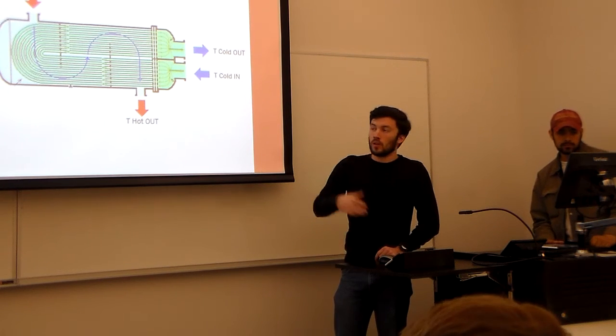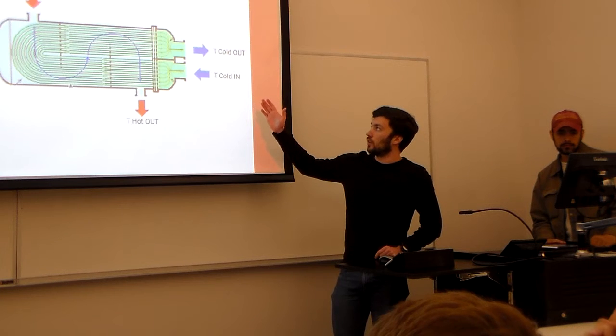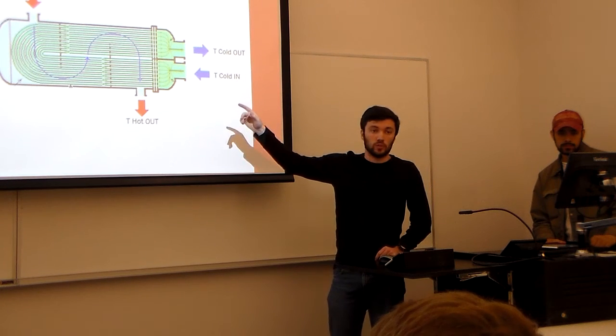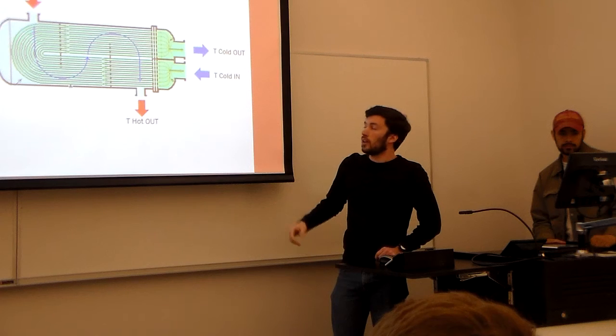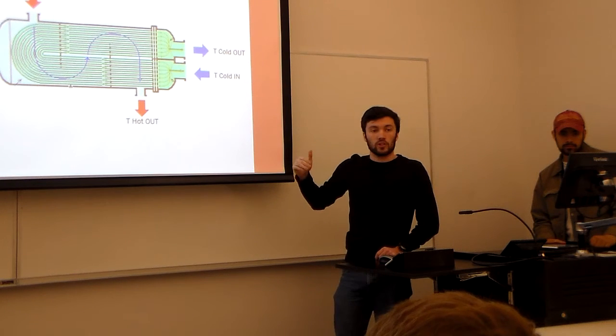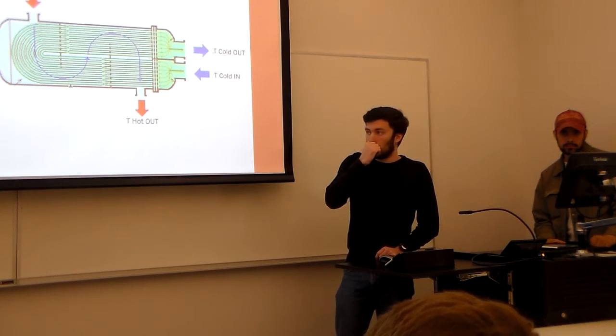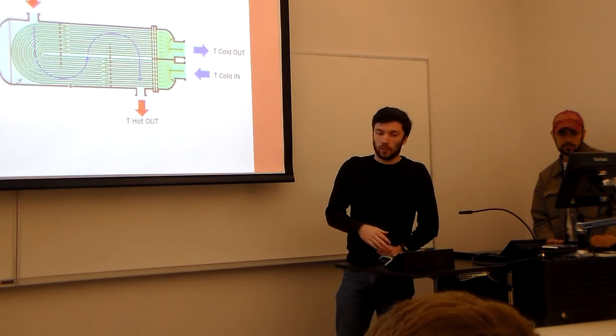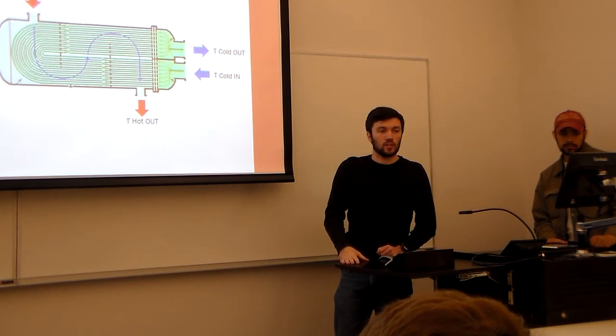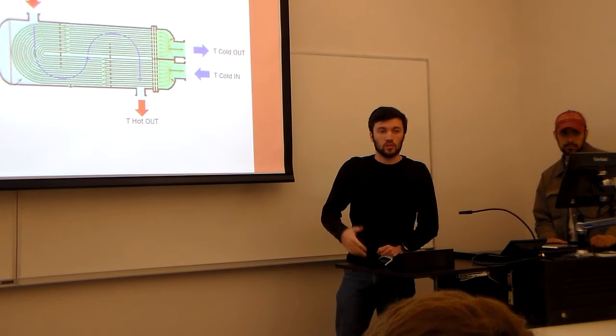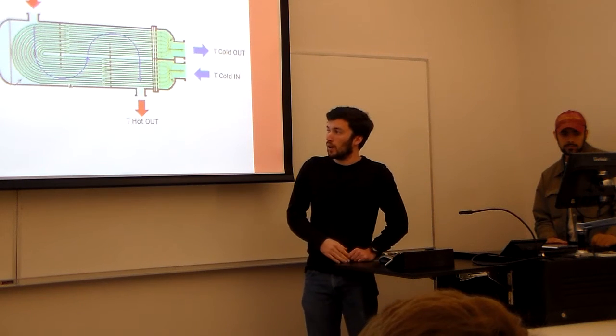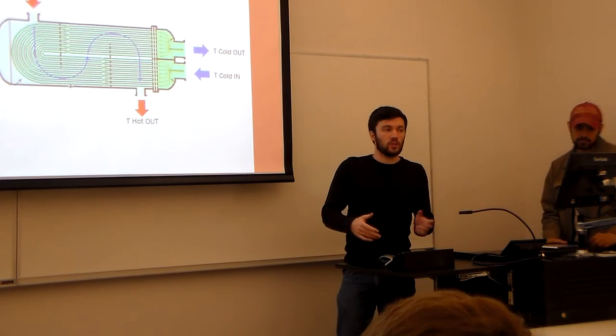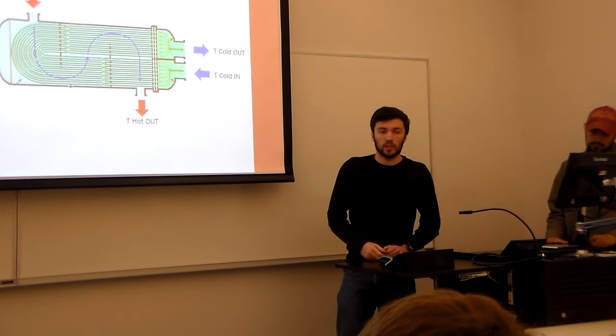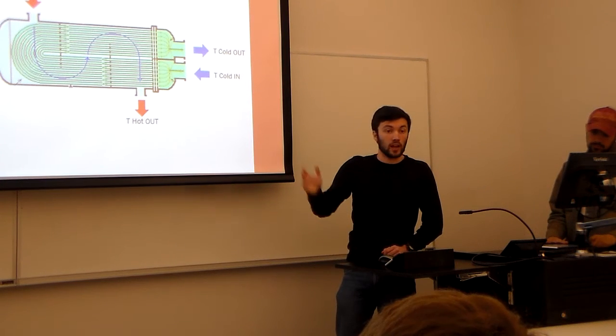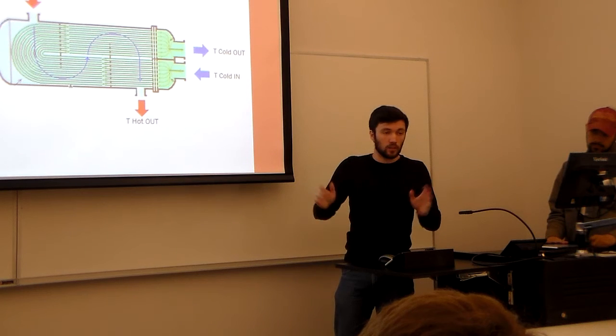So what happened was the temperature outlet of the heat exchanger, because the cold fluid is the working fluid, that's what needs to be heated up and put back in the reactor. It was about 20 to 30 degrees lower than what it was supposed to be. And it might not seem like a big issue, but the problem is that cold water has a higher density, and that increases the reactivity of the reactor because it's slowing down the neutrons, and you need slow neutrons for fission. Now, the first thing that they tried to do was rearrange the rods so that the core would continue to heat, but it didn't work. So we had to have an emergency shutdown, like the entire plant was shut down.